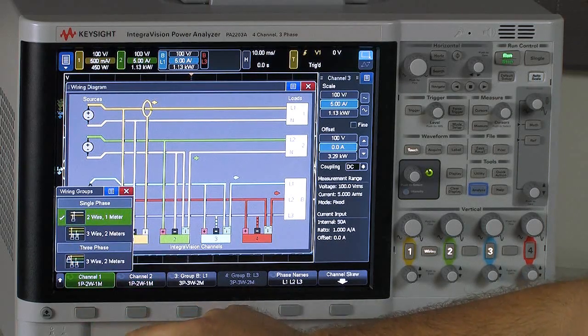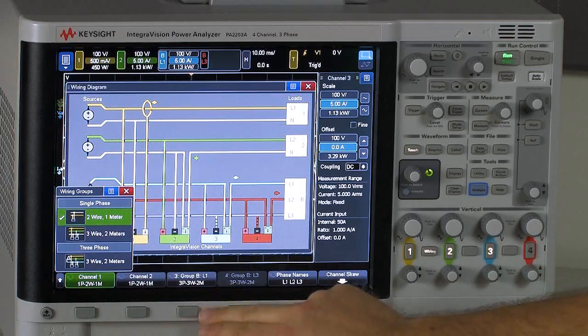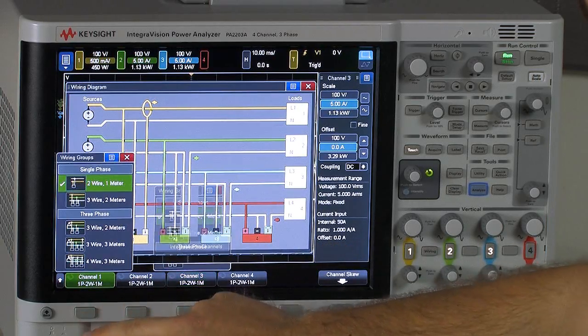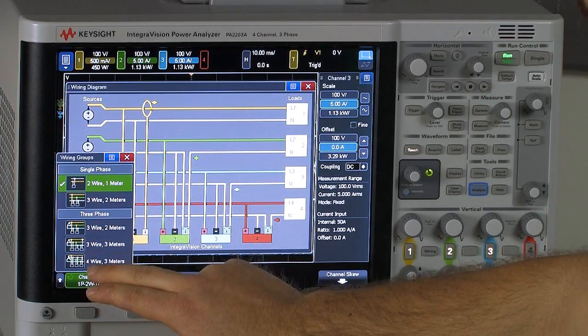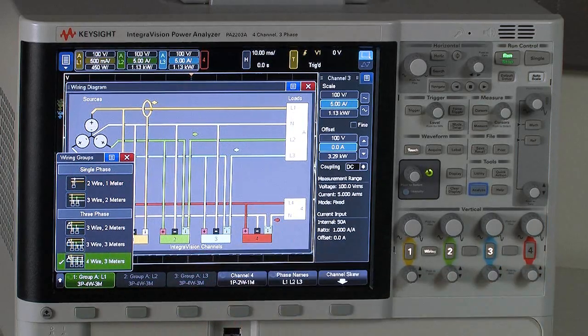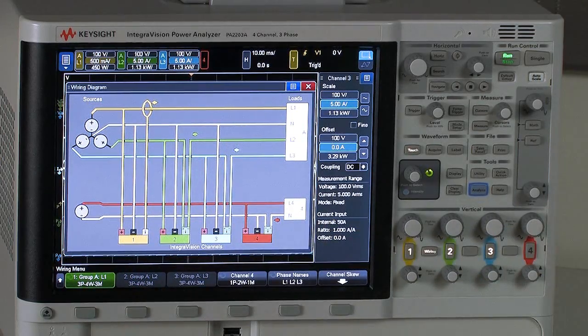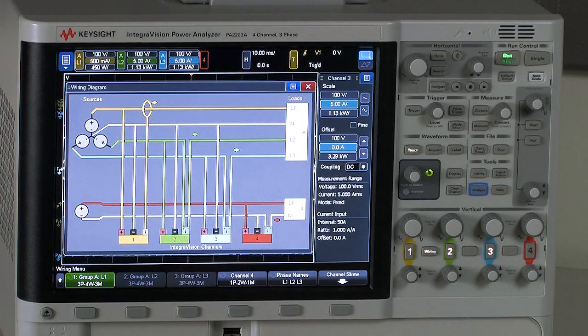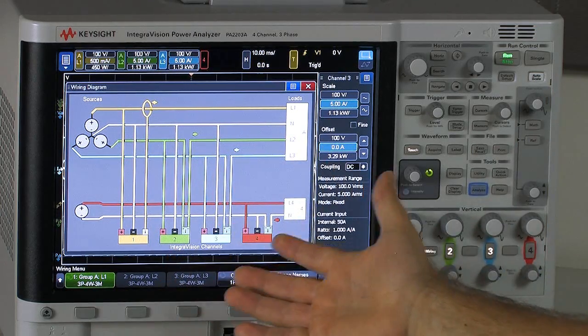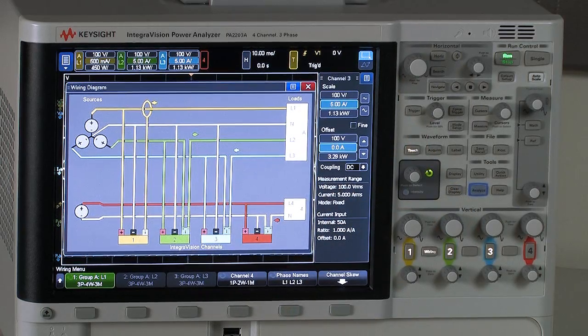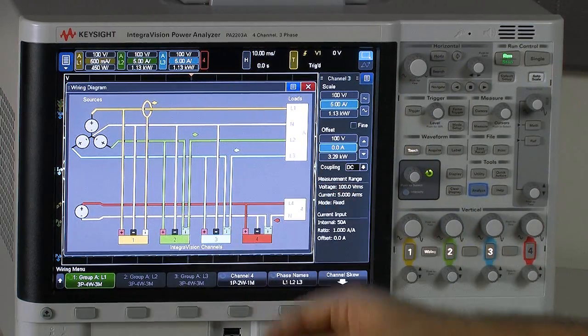The last configuration here that I'm going to show is the Y measurements or the four-wire three-meter configuration. So we can see, again, the diagram is updated. It's now set up for Y. And basically, again, you can look at the diagram as you make your connections to the instrument and proceed from there.